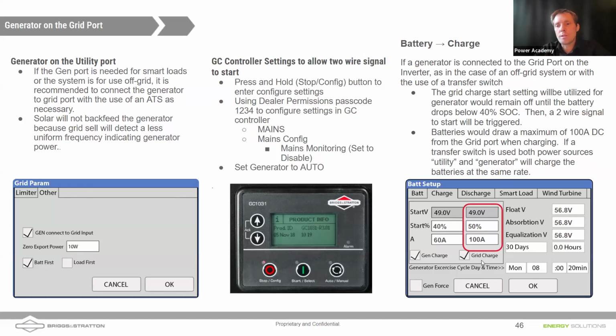Now, notice that I'm using the grid charge column for my settings for the generator. So whenever the grid is down and the battery gets below 50%, this setting could be changed. You can customize the setting, but whenever it gets below 50%, it will send a two-wire signal to start to the generator, which is connected to the grid port, right?